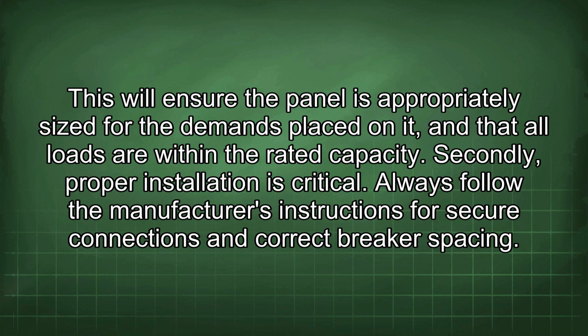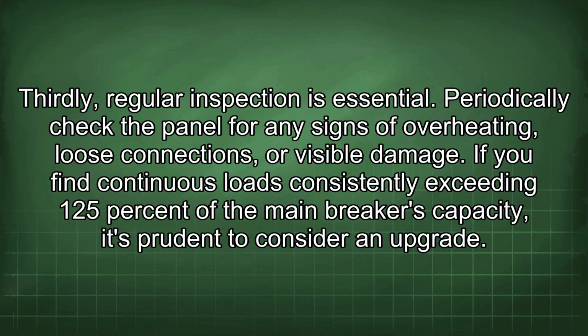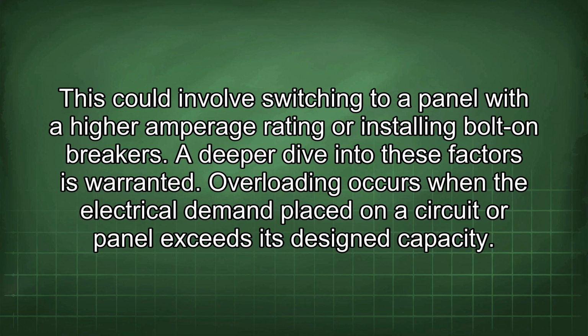Always follow the manufacturer's instructions for secure connections and correct breaker spacing. Thirdly, regular inspection is essential. Periodically check the panel for any signs of overheating, loose connections, or visible damage. If you find continuous loads consistently exceeding 125% of the main breaker's capacity, it's prudent to consider an upgrade. This could involve switching to a panel with a higher amperage rating or installing bolt-on breakers. A deeper dive into these factors is warranted.